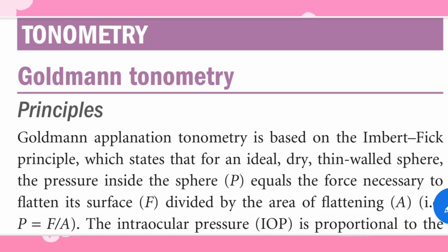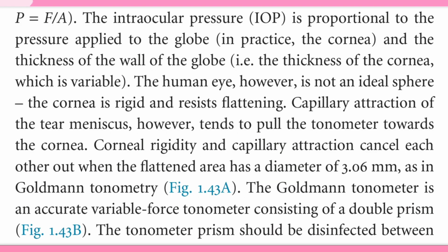Goldmann applanation tonometry is based on the Imbert-Fick principle, which states that for an ideal, dry, thin-walled sphere, the pressure inside the sphere, P, equals the force necessary to flatten its surface, F, divided by the area of flattening, A, i.e. P equals F/A. The intraocular pressure (IOP) is proportional to the pressure applied to the globe. In practice, the cornea and the thickness of the wall of the globe, i.e. the thickness of the cornea, is variable.